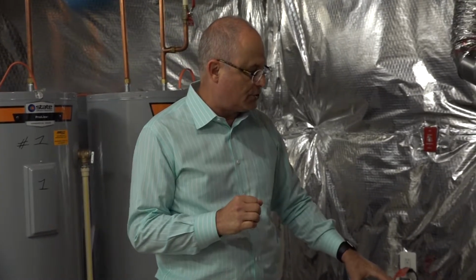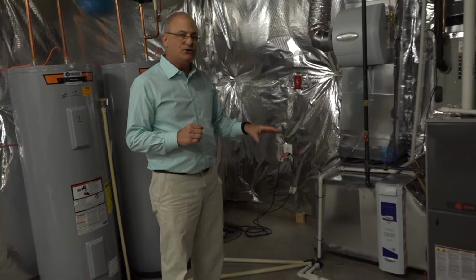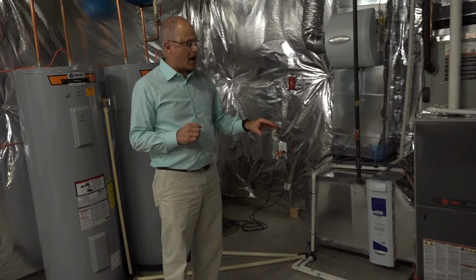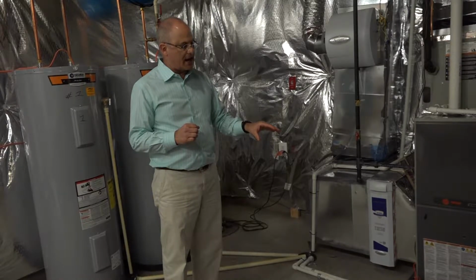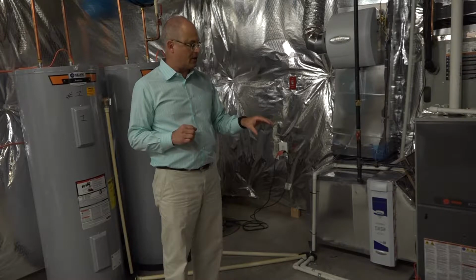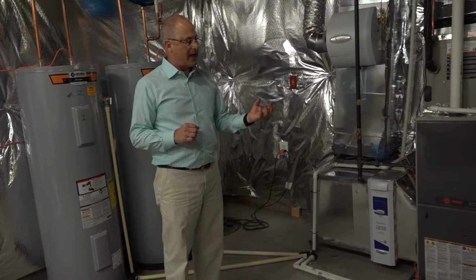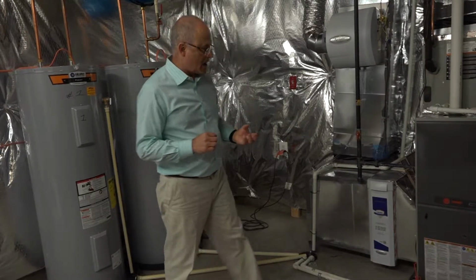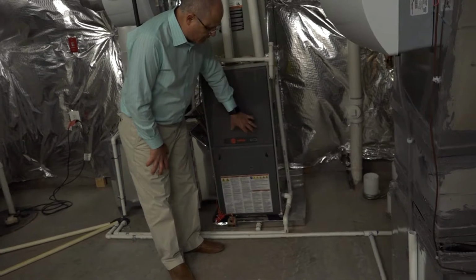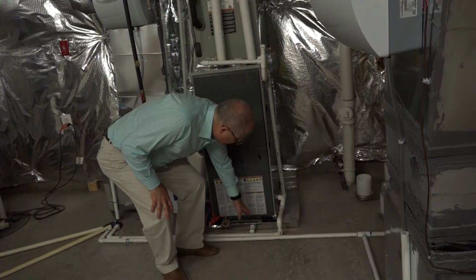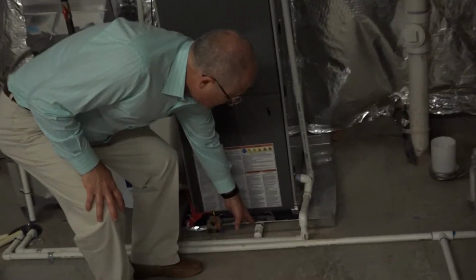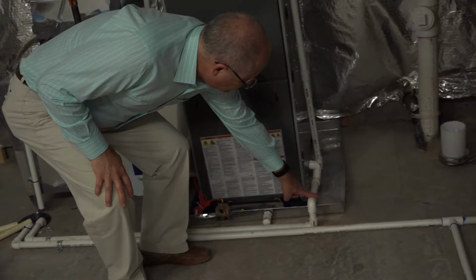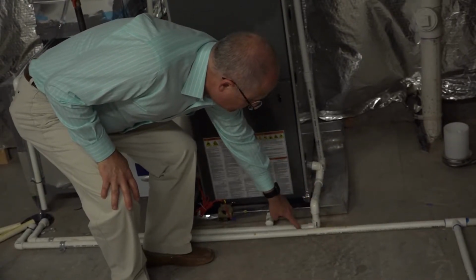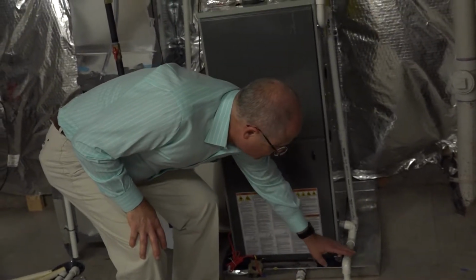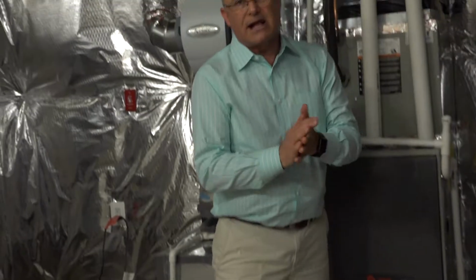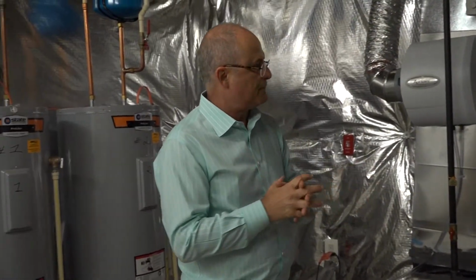Just one thing with regard to condensate drains: you should always clean the condensate drains from buildup. I would say once a year, because if there's too much buildup in the pipe, and I'll show you over here, a furnace, if the condensate ever backed up, you have the same theory, you have this catch pan, but if the condensate drain is backed up, then it's going to overflow out of the pan. So you always want to clean these condensate drains once a year, just as a preventive maintenance item.